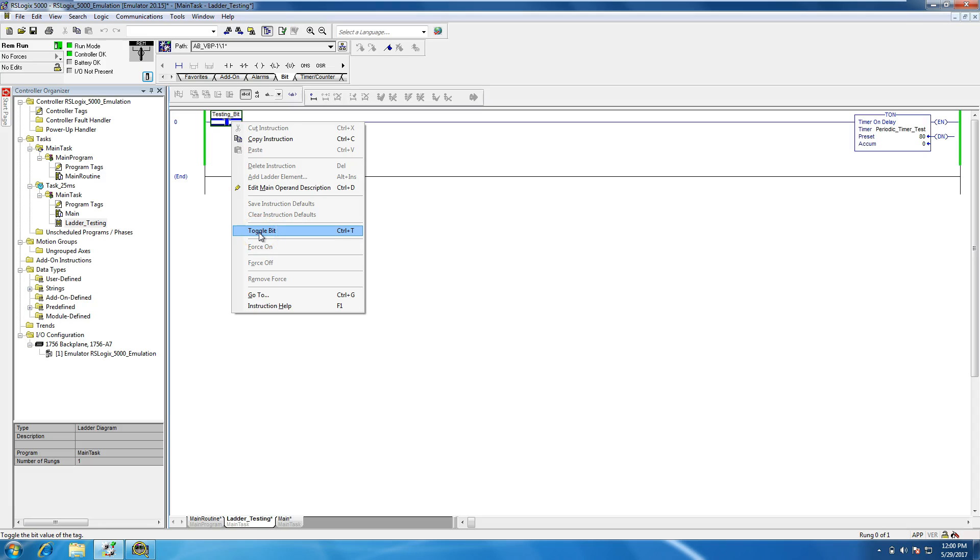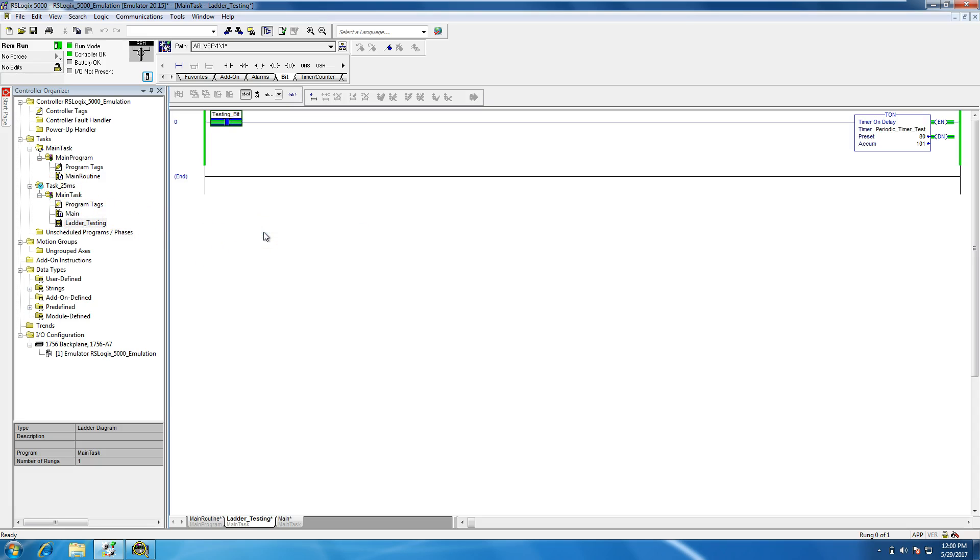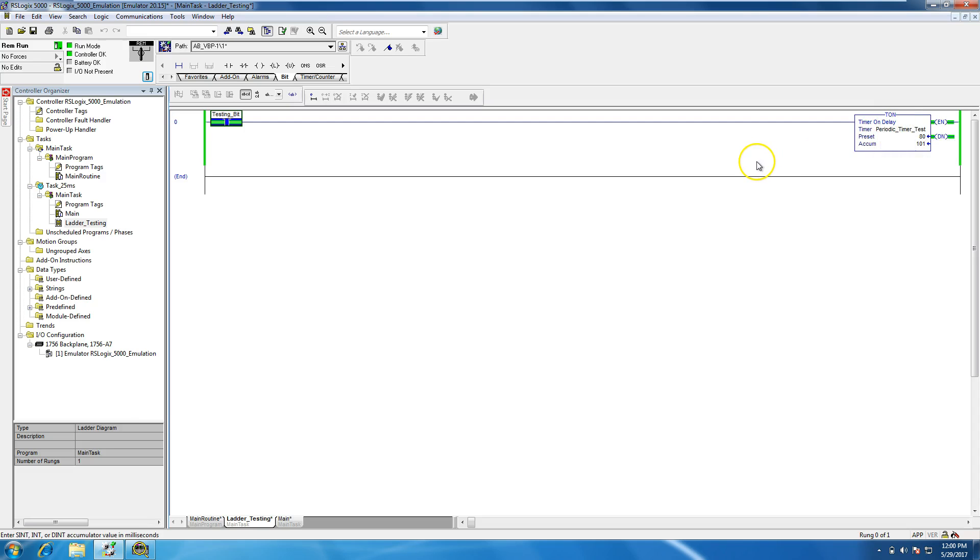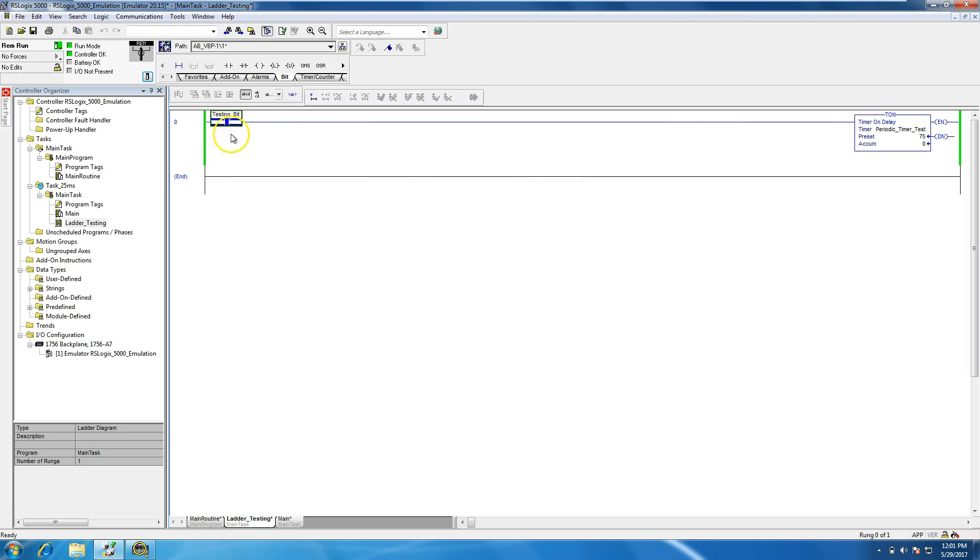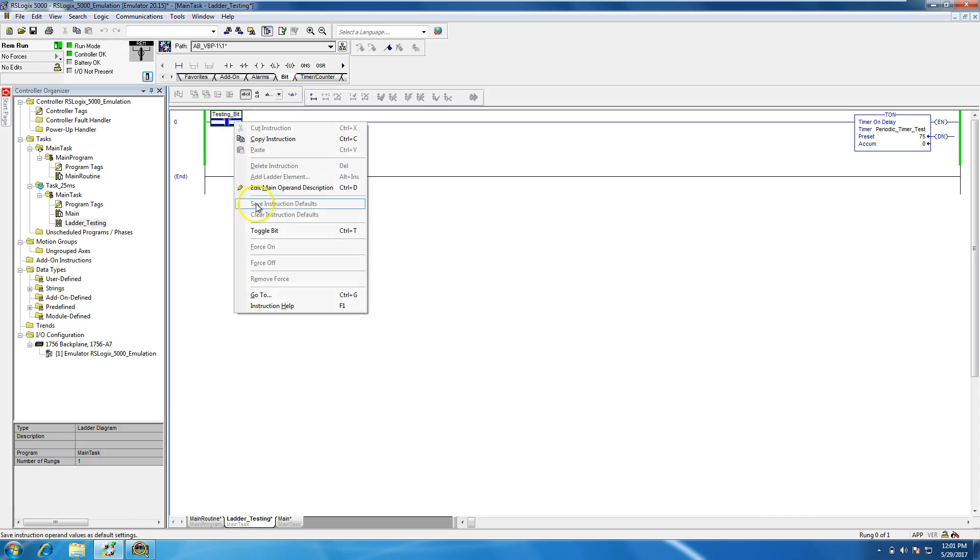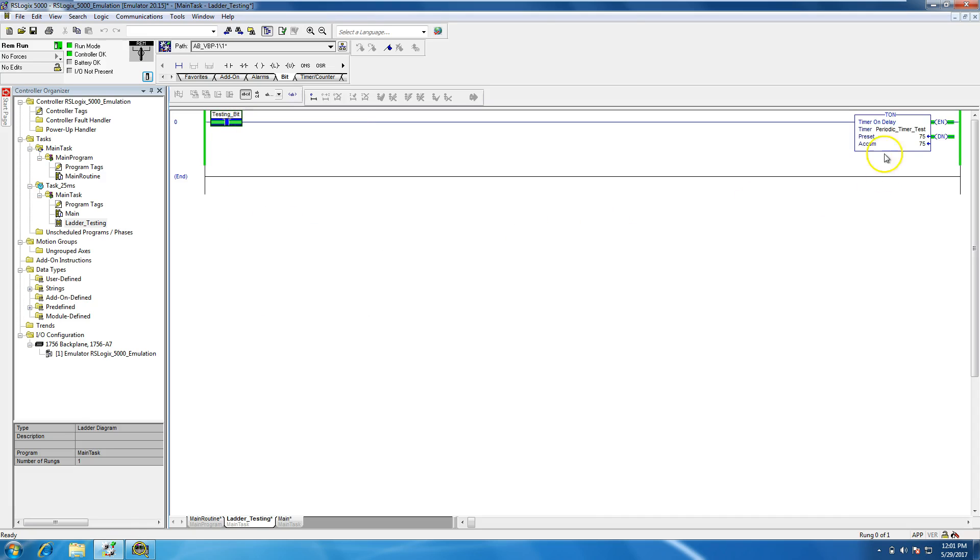So you see how this accumulation timer. The way it scans, it did 25 milliseconds at a time. So if we would have stopped it at 75, it would have stopped at 75. But being we stopped it at 80, it did not actually hit the done. It accumulated over 80, I should say that. So let's do this to illustrate that point. You see how that just stopped absolutely perfect. And this is because of the scan rate.